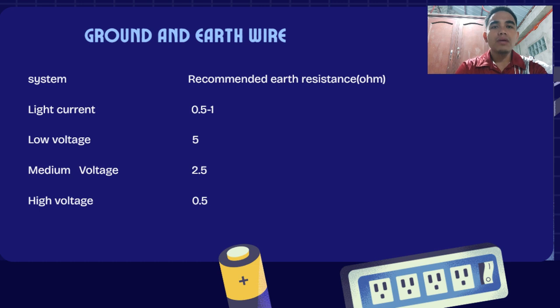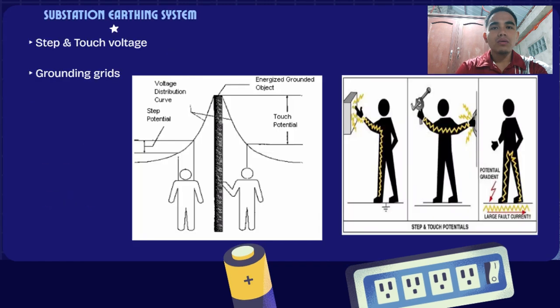So, the system's recommended earth resistance in ohms, light current. So light current is 0.5 to 1, then the low voltage is 5, then medium voltage is 2.5, and the high voltage is 0.5. So, the substation earthing system. You can see in the picture the step and touch voltage, then the grounding grids.